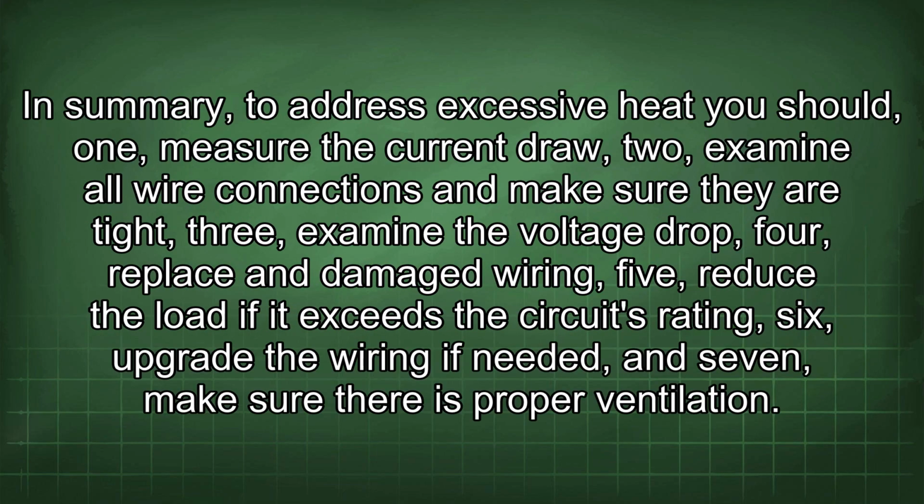In summary, to address excessive heat you should: 1. Measure the current draw. 2. Examine all wire connections and make sure they are tight. 3. Examine the voltage drop. 4. Replace damaged wiring. 5. Reduce the load if it exceeds the circuit's rating. 6. Upgrade the wiring if needed. And 7. Make sure there is proper ventilation.